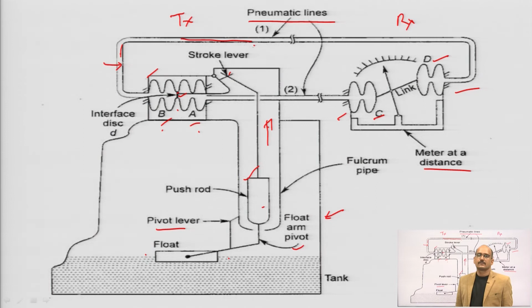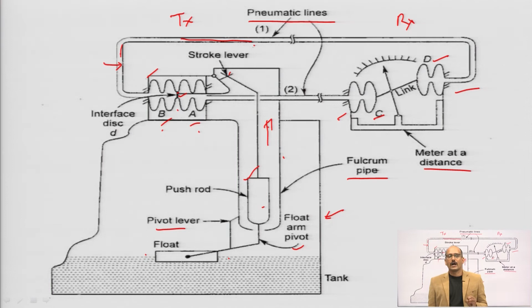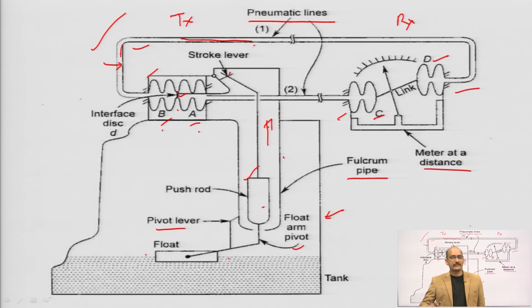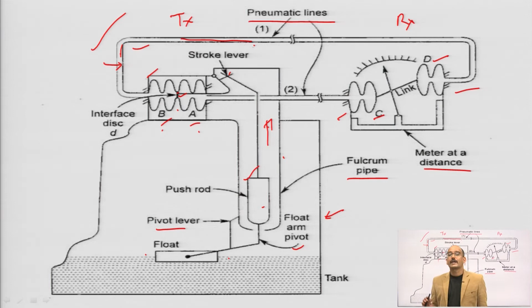So, in the pneumatic telemetry system, you understand one point very clearly, that the change in pressure is the main component which helps you detect the change in the process. Then the next point: here you are converting the complete part into pneumatic lines, and there is a drawback with compressed air, that any small leakage will destroy the complete system, and an airtight condition is required for this complete system. This will increase the maintenance of the pneumatic system, and as air compression and expansion have some saturation limits, sudden changes or minor changes cannot be observed directly.